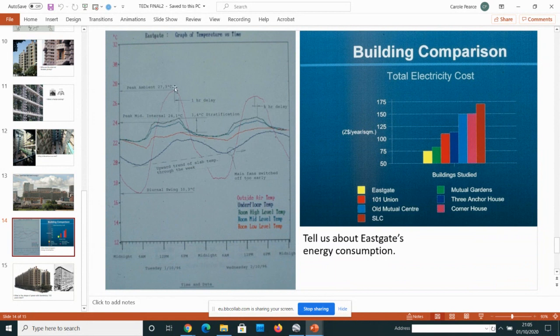Now this guy in Harare gave me this chart, and he said, look, the blue line here shows that we're not cooling, we've got the timing of the changeover from day fan to night fan wrong, because Monday is cooler than Tuesday, which is cooler than Wednesday. And then you have to notice that meant adjusting the timing so that it was slightly different for each day. And then we decided that the changeover should be controlled by thermometers.